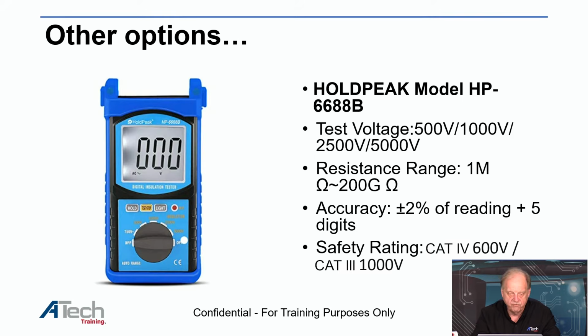This one has a test voltage of 500. If you look at it, it has 1,000, 2,500, and 5,000 volts. Resistance reading on this one goes from 1 megohm to 200 gigaohms. Accuracy, I hate it when they write this, but it's 2% of the reading plus 5 digits. If you're looking at that information, it's kind of interesting. I'd like a breakdown of how to do this. Safety reading is 600 to 1,000 volts, again on Cat.